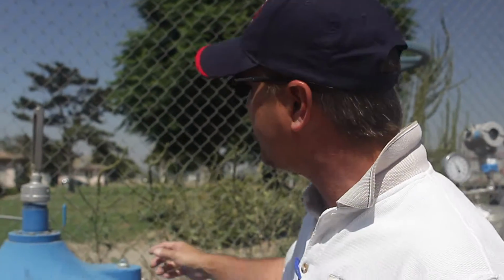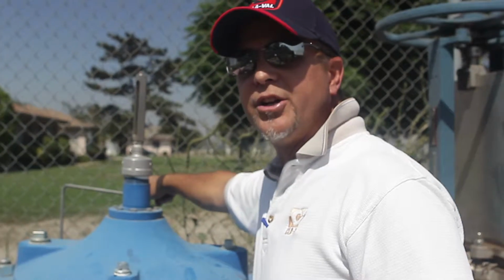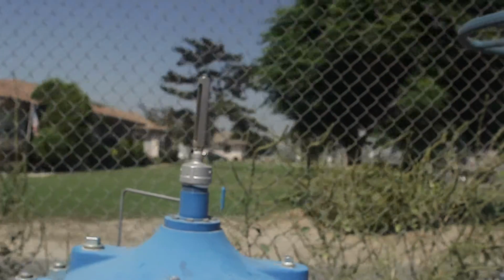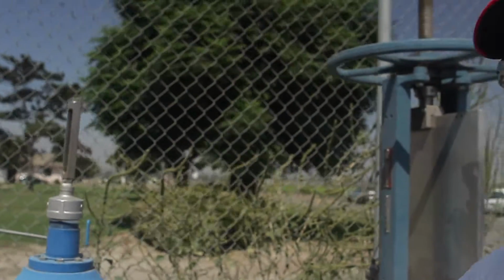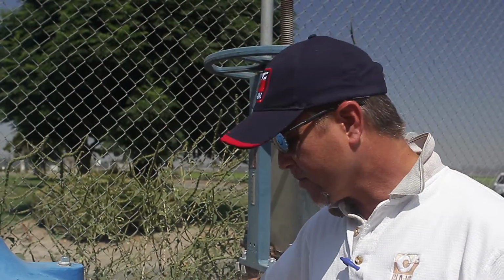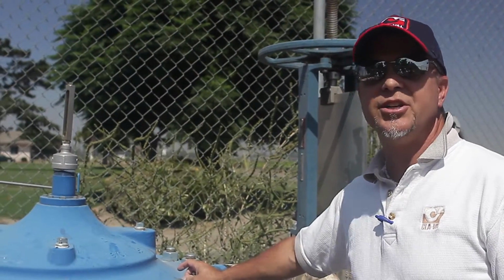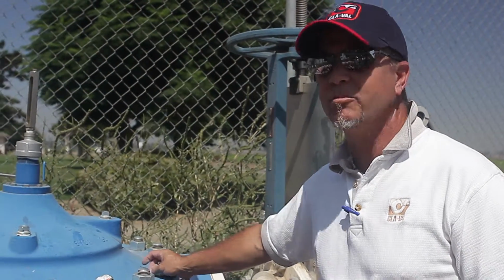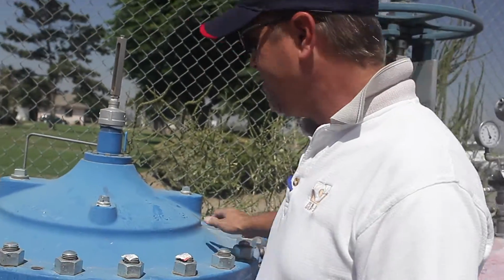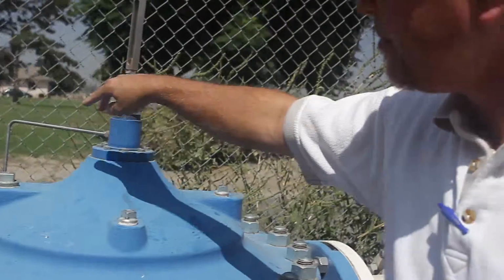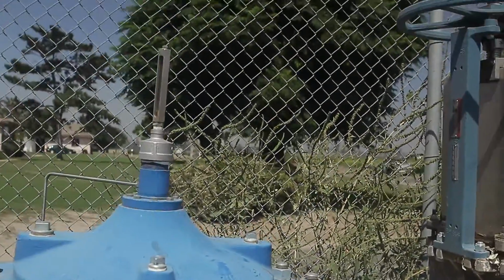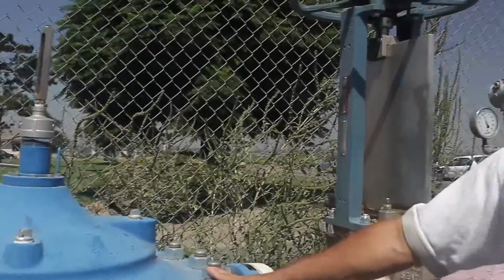This is our cover connection, and part of that connection goes to the 3/8" ball valve on the main valve cover. After that 3/8" T, the cover connection, we have a 3/8" model CRD. This is a pressure reducing pilot. It is direct acting. And right off the discharge of the pressure reducing pilot, we have a pressure gauge. And so that tells us directly what the downstream pressure is.